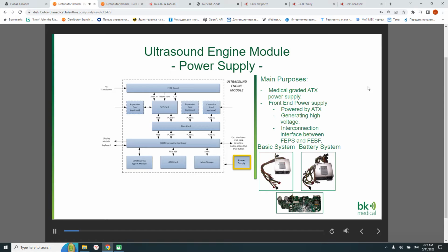The scanner has a built-in power supply. There are two different versions, one for the basic system and one for a battery-driven system. It's medical-graded ATX power supplies, and we also have a front-end power supply. It's powered by the ATX and is generating the high voltage that we need to use on the front-end boards. To allow the PC and the SCP to communicate with the front-end beamformer board, we have introduced the interconnection board. The board is acting as a bridge between the front-end power supply and the front-end beamformer board, and is only used for communication signals.